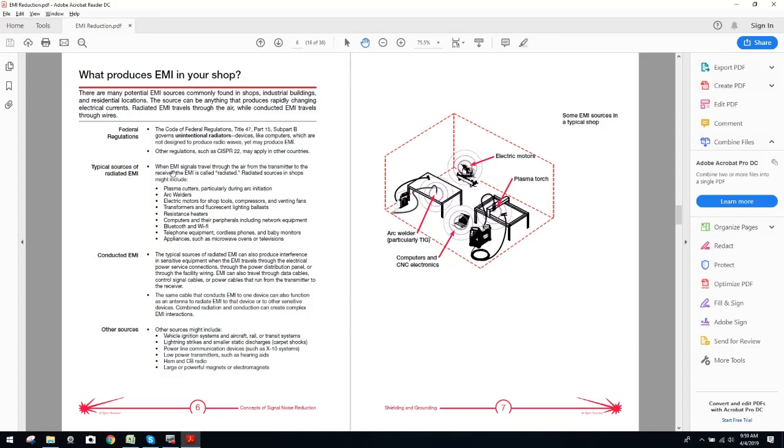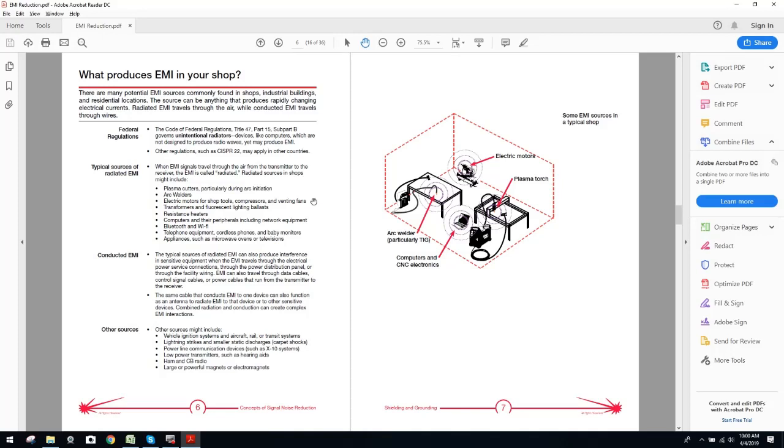Over here, typical sources of radiated EMI. When EMI signals travel through the air from the transmitter to the receiver, the EMI is called radiated. Radiated sources in shops might include, now I hope everybody is listening closely, plasma cutters, particularly during arc initiation, arc welders, electric motors for shop tools, compressors and venting fans, transformers and fluorescent lighting ballasts, resistance heaters, computers and their peripherals, including network equipment, Bluetooth and Wi-Fi, telephone equipment, cordless phones and baby monitors, appliances such as microwave ovens or televisions. Guys, that basically covers everything. I mean, I'm going to be honest with you. If you plug in anything, you're going to have EMI. The question is how much EMI you're going to actually have. Again, conducted EMI, the typical sources of radiated EMI can also produce interference in sensitive equipment when EMI travels through the electrical power service connections, through the power distribution panel or through the facility's wiring.